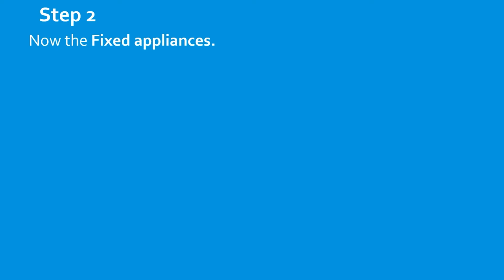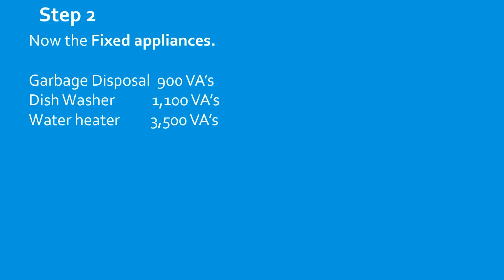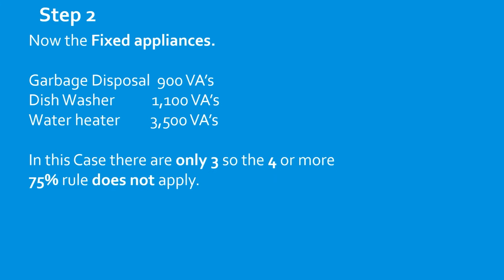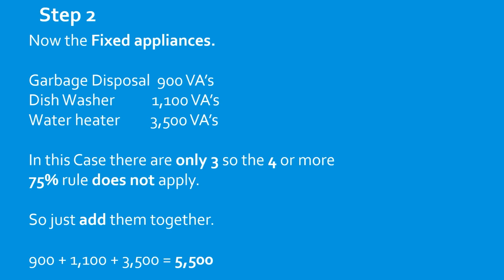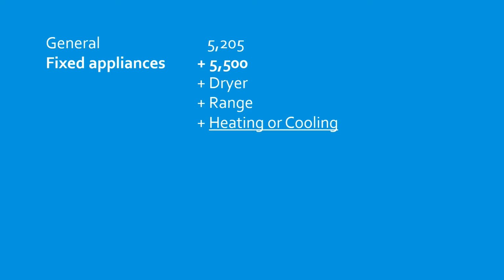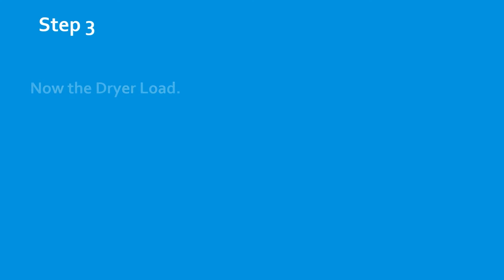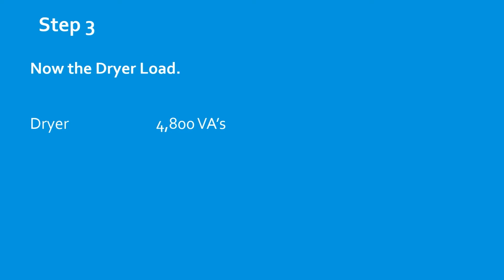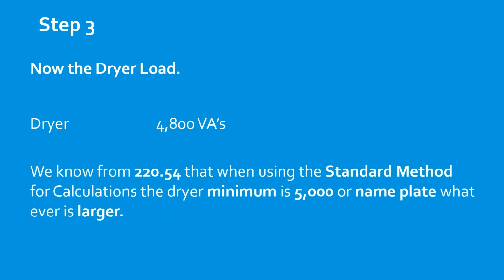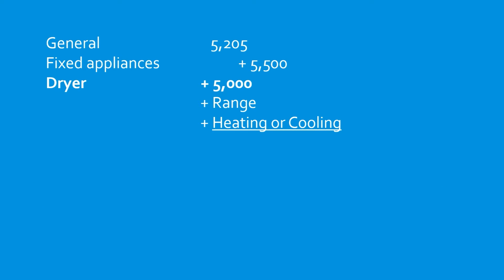Now the fixed appliances. We have a garbage disposal, a dishwasher, and a water heater. In this case, there's only 3, and we need 4 or more to apply the 75% rule, so it does not apply. So we just add them together. Okay, and that's going to give us 5,500 VAs. Okay, now we're going to do the dryer. Now the dryer load. Dryer, 4,800 VAs. We know that from 220.54 that when using the standard method for calculations, the dryer minimum is 5,000 VAs or the nameplate rating, whichever one's larger. So we add 5,000 for the dryer.